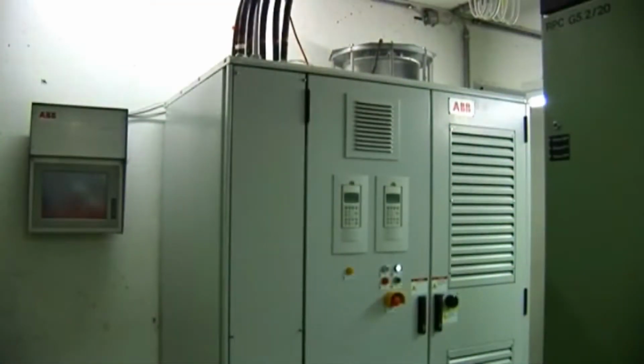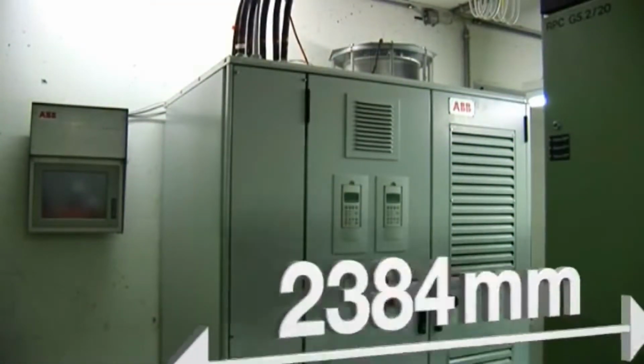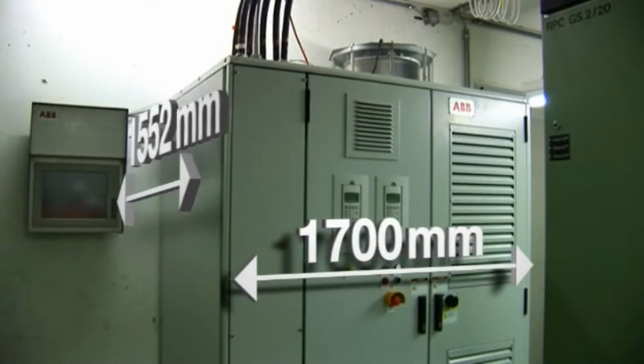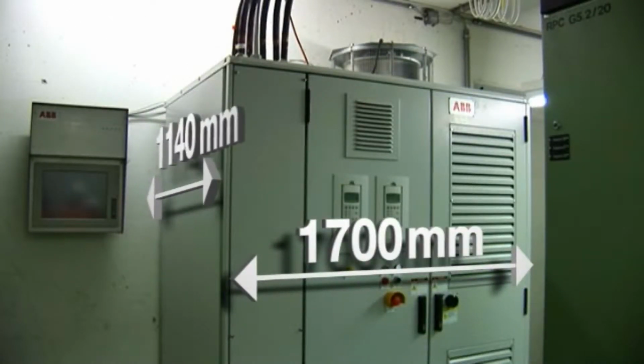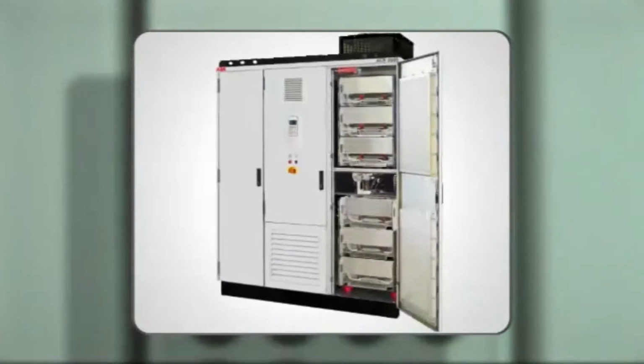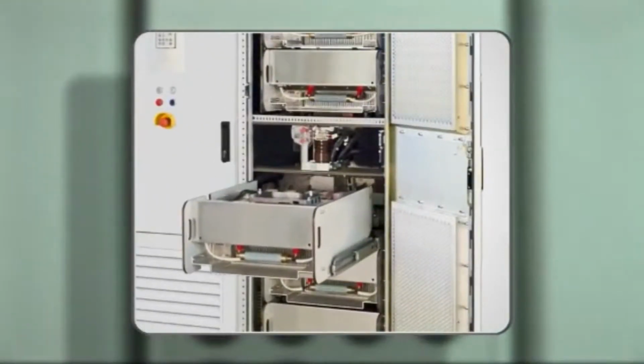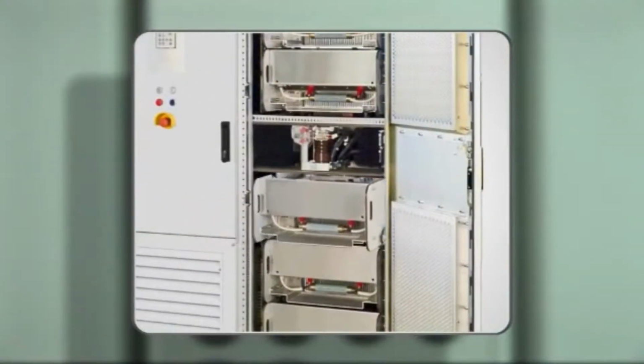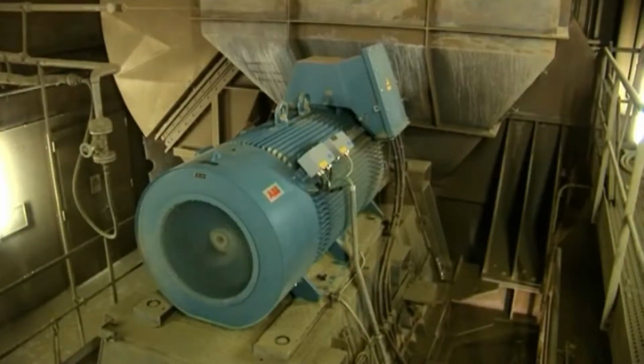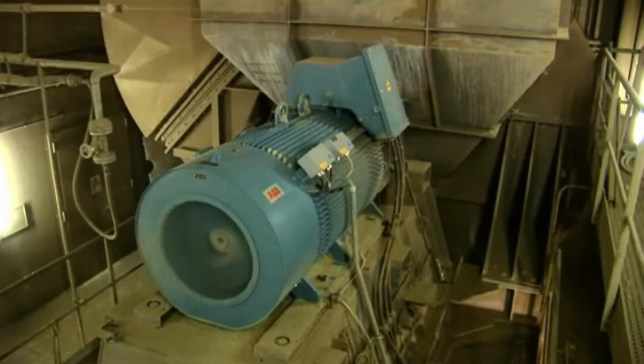Enter the ACS 2000. With a footprint of only 1700 millimeters wide by 1140 millimeters deep, the drive is much smaller than the Cascade drive. It is also designed with replaceable phase modules, which allow the end user to rapidly replace a module within minutes. As cement making is a continuous process, the drive needs to operate 24 hours a day and only be taken offline at planned maintenance intervals.